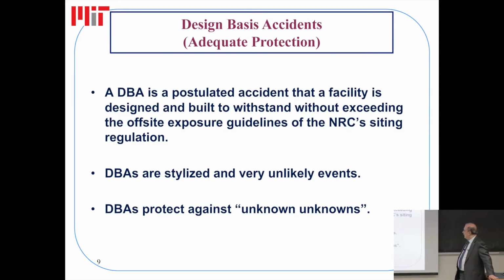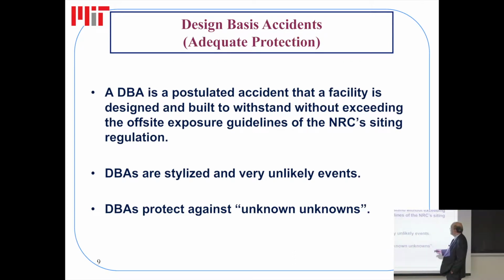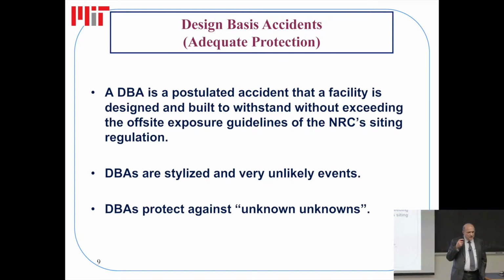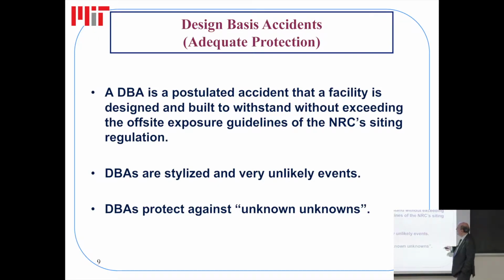An important element of the traditional approach is, again, the concept of design basis accidents. And the definition is here. It's a postulated accident, in other words, regardless of its frequency, that a facility is designed and built to withstand without exceeding the off-site exposure guidelines of the NRC. They are very stylized and very unlikely.